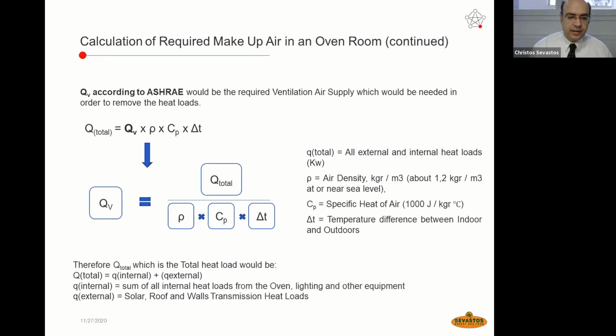And which is the overall heat? The total heat is the heat coming from the internal sources, tunnel oven, or whatever else we're going to have as a heat appliance, plus the external heat loads, which are coming from the solar radiation heat, the roof, and the walls transmission heat loads. So the first step is for us to calculate internal and external heat loads. And this equation is going to allow us to define the proper air ventilation in pressurized ventilation systems in the oven.